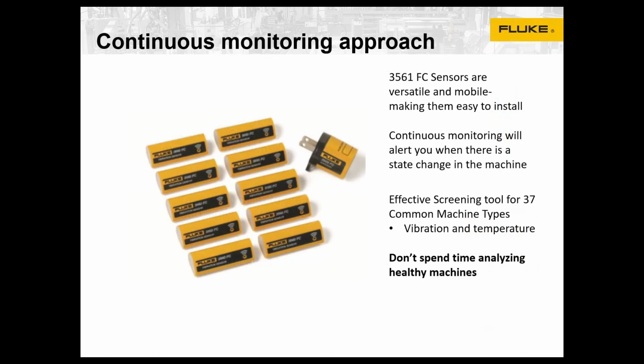For assets that are difficult to reach or unsafe to reach, we have vibration sensors, which can be mounted at varying locations on equipment that will transmit their readings and also give you that same good, satisfactory, unsatisfactory, unacceptable alarm flags. This might be used in hard to reach spaces where it's difficult to make measurements with a handheld tool, or unsafe environments.